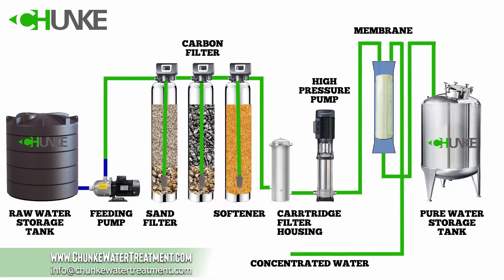First, water is sent from the raw water tank by the feeding pump to the sand filter to remove bigger particles and suspended solids — we use quartz sand or special filter media. Second, water goes to the carbon filter to remove odor, taste, organic compounds, and chlorine — we use activated carbon or anthracite.